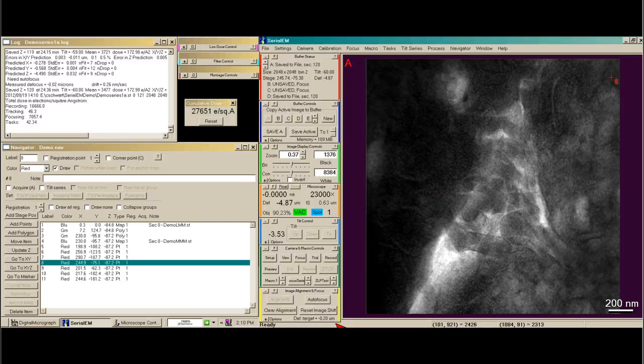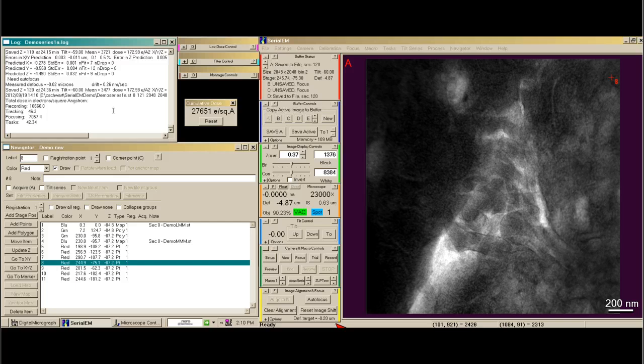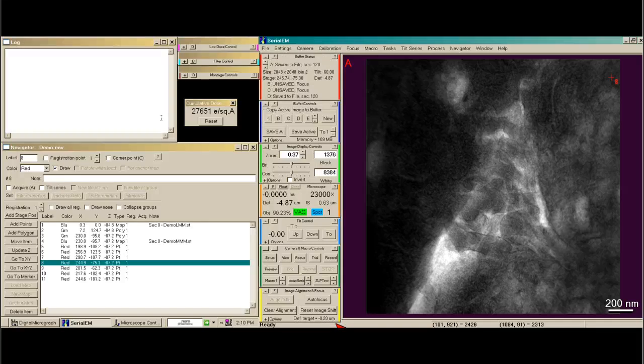It took almost 25 minutes to take the entire tilt series, and the log file tells you information about your tilting and these kinds of things. This gets put into a log file so that your administrator could look through and see what kinds of data people were collecting. It will also give you a list of all the dose. Between tilt series, it's a good idea to close and save your log file and then open a new log so that each tilt series has its own log file. I like to save the log files because they're very small files, and it gives you all the information about the tilt series — so if you ever have to go back and look up what defocus you used or what was your tilting increment, it's all there and accessible.